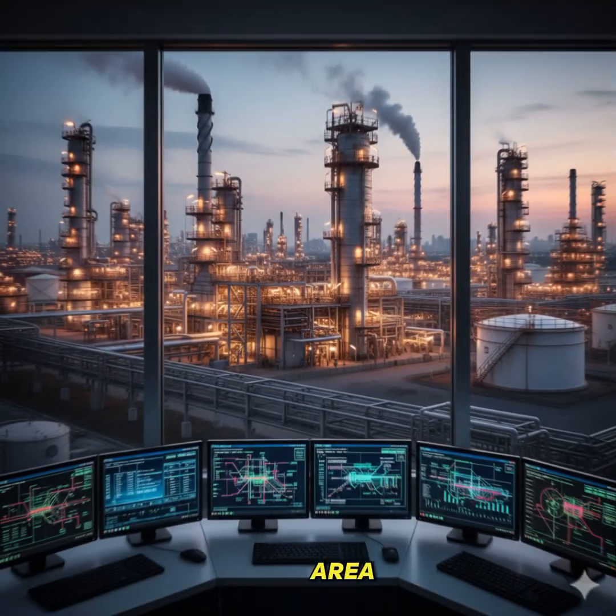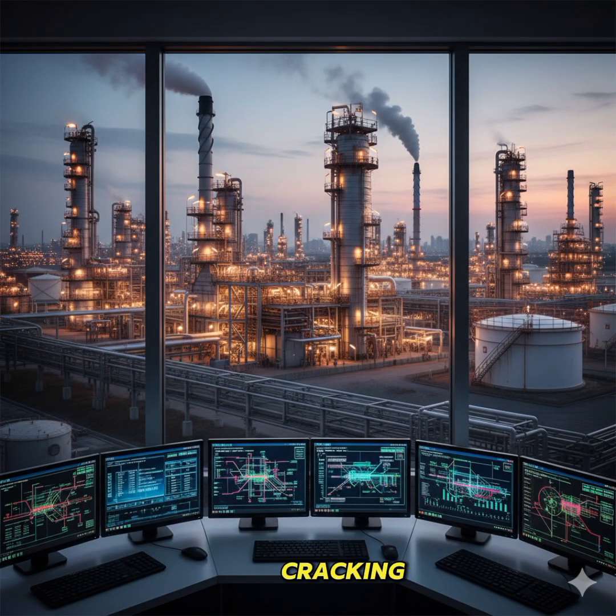Each process area, like the distillation column or cracking unit, has its own controller that continuously adjusts valves, burners, and pumps. All these controllers are networked, allowing operators to monitor and optimize performance from a single screen. Even if one controller fails, others continue to operate, ensuring plant safety and reliability. That's DCS, distributed, fast, and built for continuous industrial control.